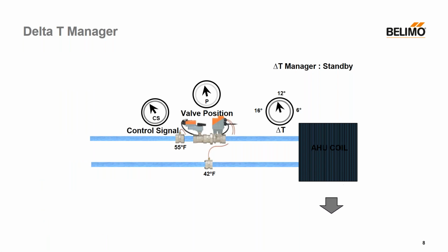Now that we know how that system works, we can look quickly at how the actual energy valve works. So this is explaining the smarts, or the logic that we referred to earlier. In this graph, if I start on the bottom, I have the supply coming in the bottom of this example. The bottom pipe shows 42 degrees. It passes through my air handler unit on the right. I take a heat exchange as the air passes over it, and I go out the top on my return through my energy valve with 55-degree water. In this example, 42 in, 55 out, a nice 13-degree heat transfer.